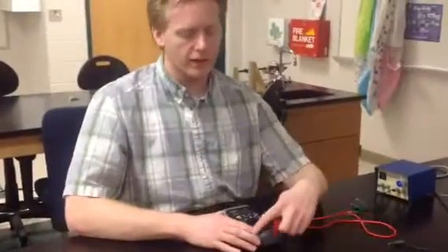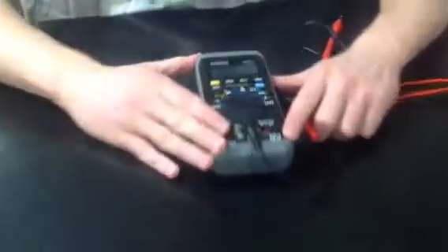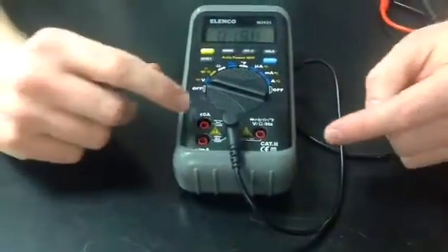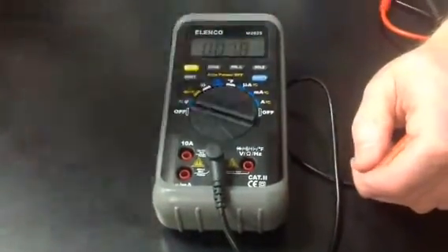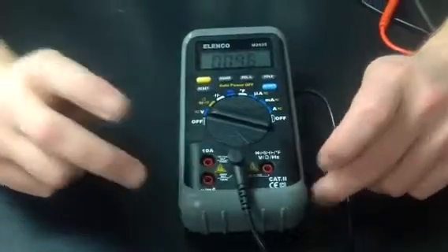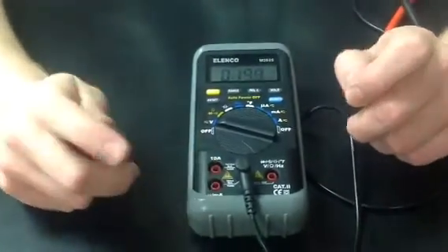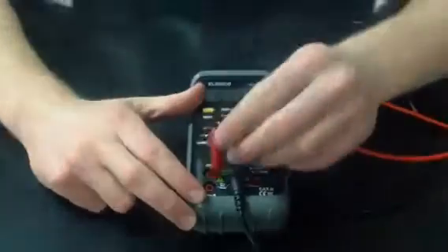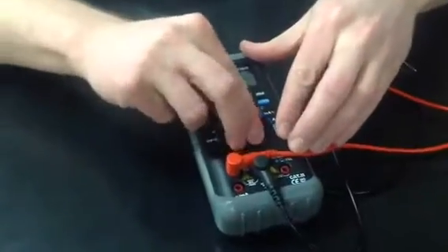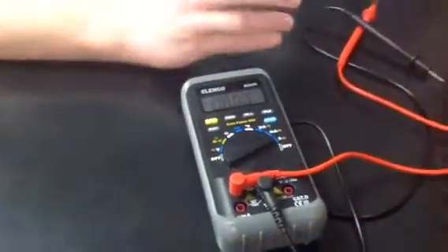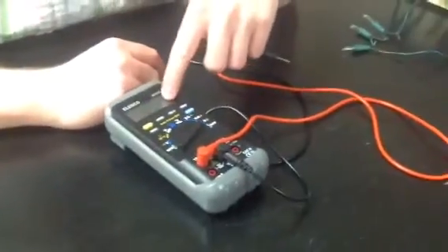For measuring current, we have to move the probe out of the voltage indicator and into one of these two current options. Current is measured on this multimeter either through a large 10 amp measurement or through a much smaller micro or milliamp measurement. The purpose of the micro milli is to get more precision, but if you run too much current through those, you're going to blow the fuse on the device. So we always start in the 10 amp circuit and turn our dial to measure in whole amps. If it turns out the current is too small to register, it'll show 0 on this display, and then we'll move into a more sensitive reading. But for now, we're going to start always in the 10 amp circuit.